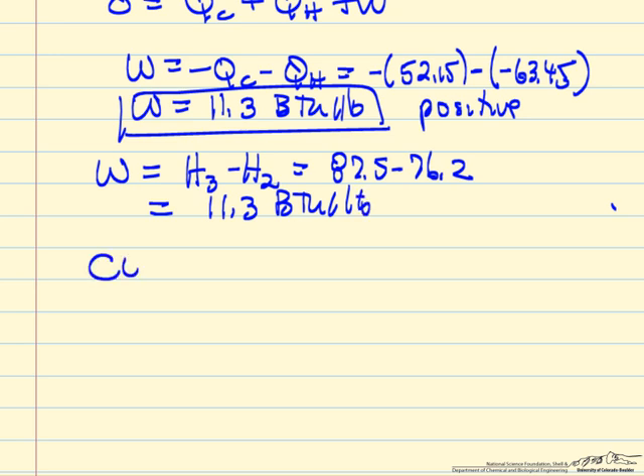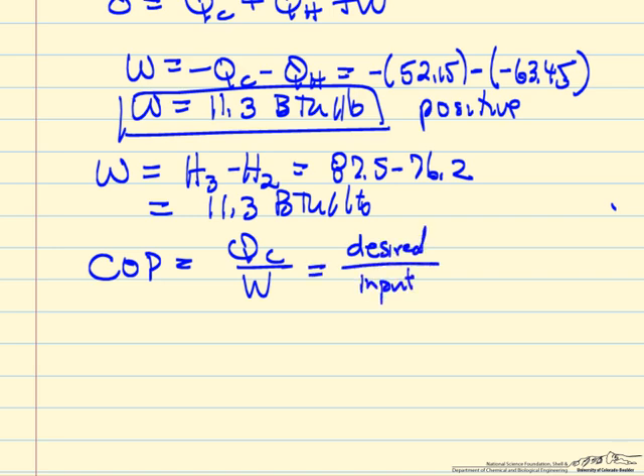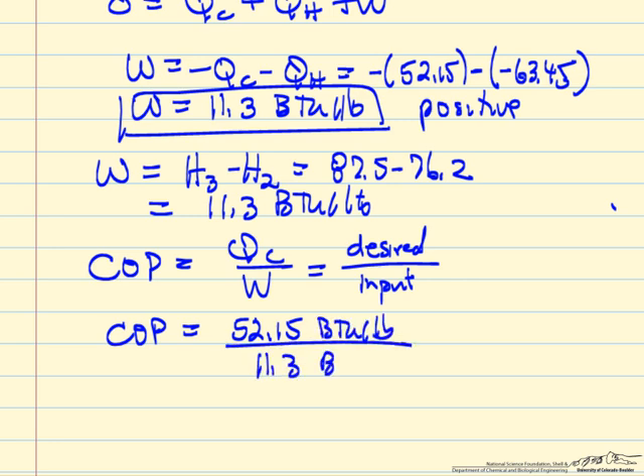The coefficient of performance is defined as QC over W. You can look at this as what is desired for a refrigerator, and this is what we have to input, what we have to pay for. So the coefficient of performance is 52.15 BTUs per pound divided by 11.3 BTUs per pound. This indicates how efficiently we use the work. For every unit of work we put in, we transfer 4.6 units from the low temperature, which is our objective.